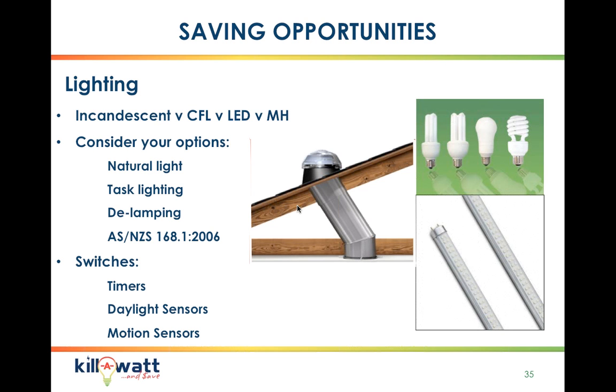Consider your options for natural light, and what your lighting is relative to the job you're trying to do. If you've got a storeroom with massive lighting, or an office that doesn't have enough, delamping is a practice of removing some lights while still maintaining minimum standards. You can see the standard level there of AS 168.